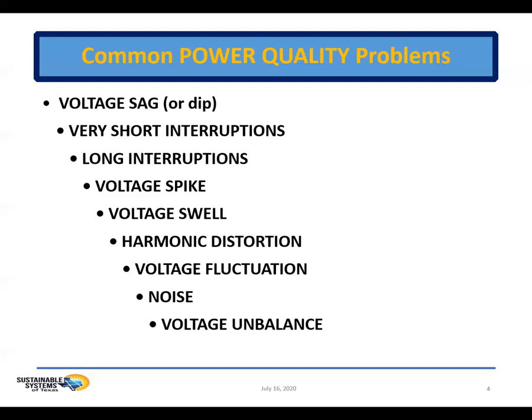Harmonic distortion. This is a modern day problem which developed with the developing technologies, where voltage or current waveforms assume non-sinusoidal shapes. The resultant waveform corresponds to the sum of different sine waves with different magnitudes and phases, having frequencies that are multiples of power system frequency. Next, we have voltage fluctuations. This is an oscillation of voltage values, amplitude modulated by a signal with frequencies of 0 to 30 hertz. Noise is the superimposing of high frequency signals on the waveform of the power system frequency. And closing with voltage unbalance, we have a voltage variation in a three-phase system in which the three voltage magnitudes or the phase angle differences between them are not equal.